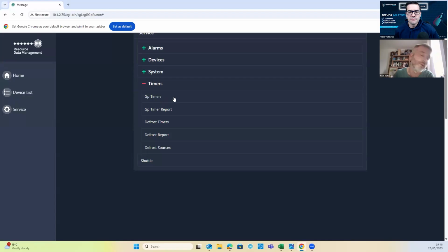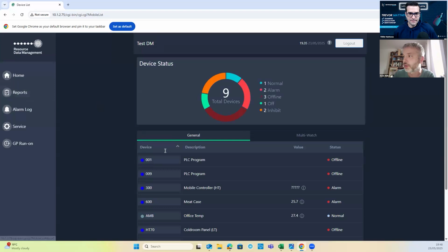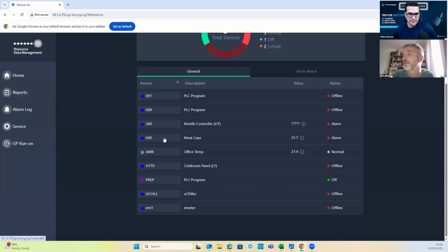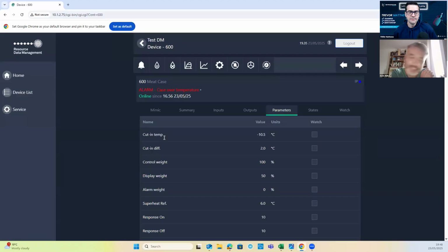Same with lights. If you want all your lights to come on together, you set a timer. I won't do it today because it's a whole other topic. Set the GP timer up, set your light signal on your cases to remote, and all the lights will go on and off. That's really useful where you've got remote access to a store and they're saying, we want to stay open another hour's trade-in. Can you put the lights on? You don't want to adjust the light timers on 100 fixtures. You just do it once on the panel.